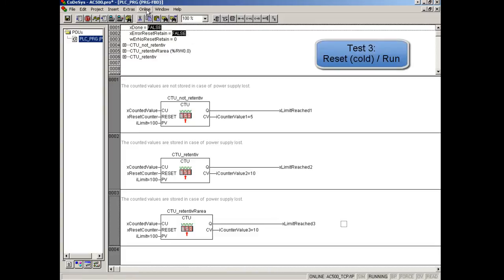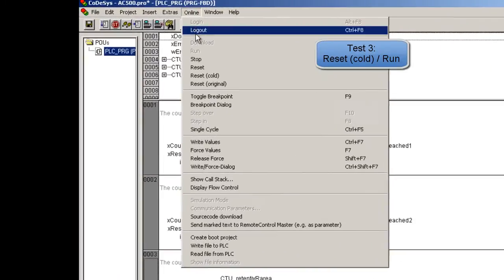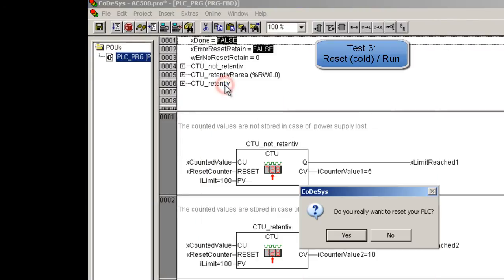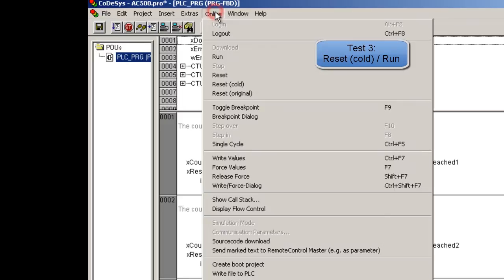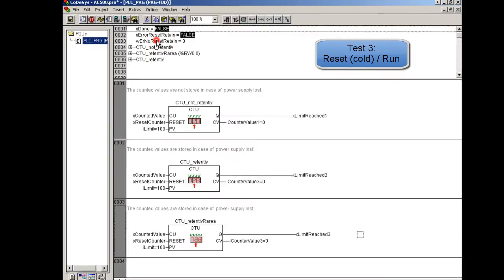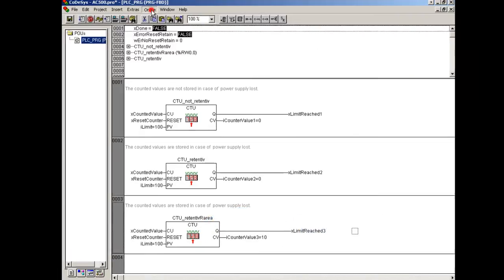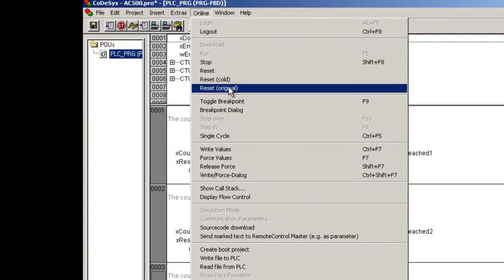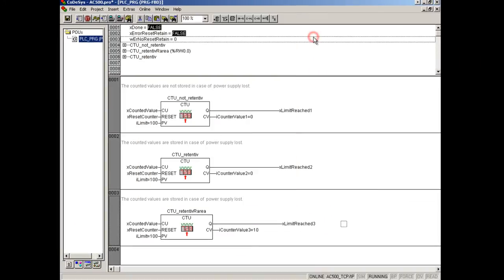Now, what happens after reset cold and restart? We recognize that the reset cold is initializing all variables, but the %R area keeps its values. The reset original would erase the project, the whole configuration and all variables. For this it is not relevant for the test and we won't try it.